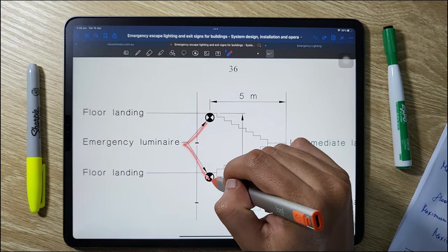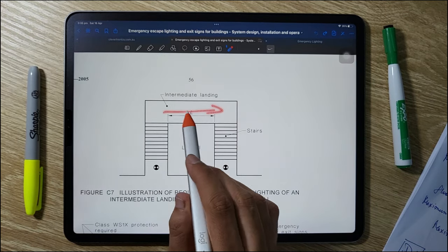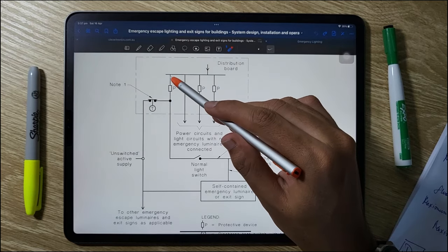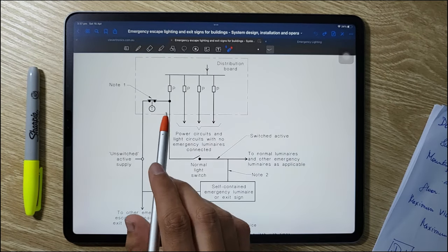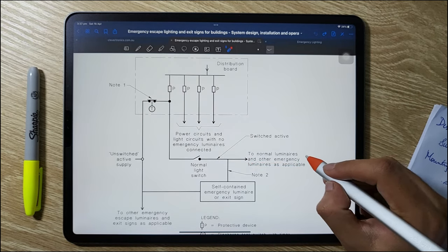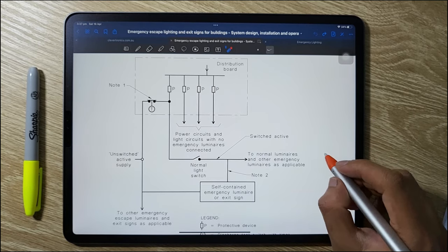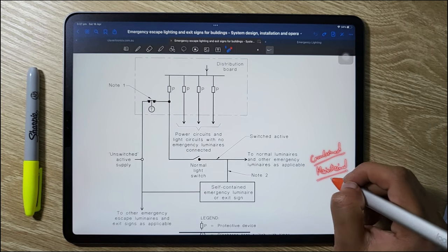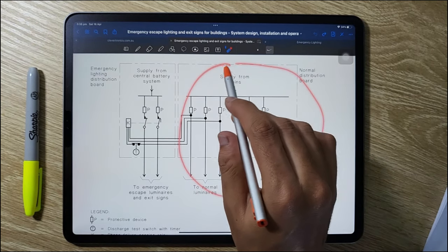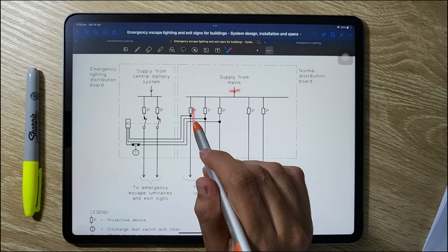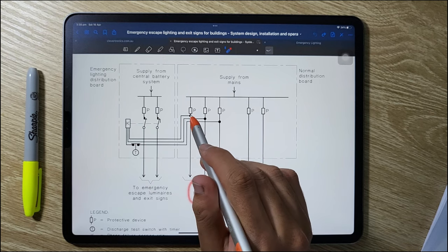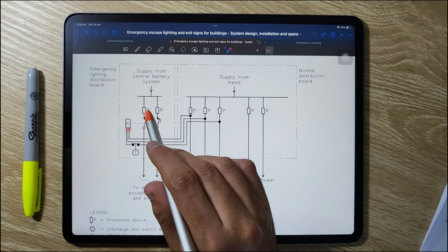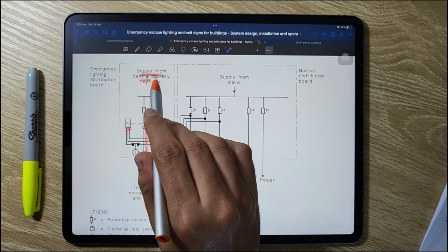Emergency luminaires on a stairway should be on the floor landing, not on the intermediate landing. For the distribution board with a self-contained system, four phases power normal lighting and power circuits, and these are also connected to emergency lighting. Maintained or non-maintained emergency lights are powered by a self-contained battery system upon phase failure. In the central supply system, the mains supply powers normal luminaires only, and a phase failure relay detects supply failure and powers the emergency luminaires from the central battery system.